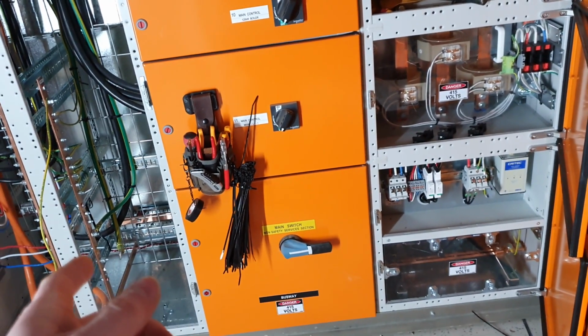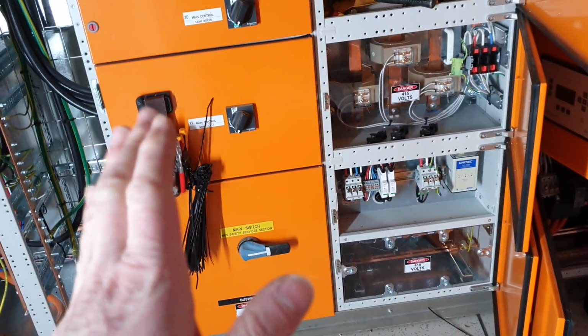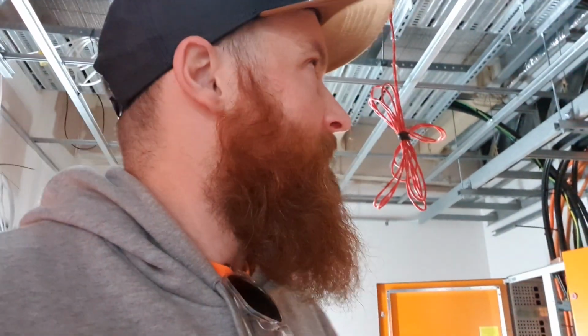So I'm going to take that piece of cable home and see if I can find out what the actual issue was - it's got to have a pinprick or something. We went down, chopped it, tested it from that end, and it cleared right out. Absolutely, I was panicking honestly - rerunning one of those cables, the cable alone is probably worth about 10 grand for one of the sets. Not one of the sets, one of the cables out of one of the sets - 10 grand.